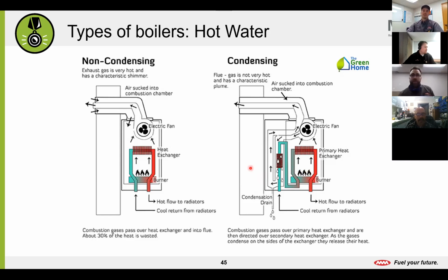All right. So boilers. I know Joe was talking a little bit about that on a condensing loop, right? If you're all running in heating, you're absorbing heat from that water. Eventually that water is going to dip below that 60-degree mark. That's where your boiler comes into play. So you'll have a thermostat mounted to your water loop and set for 60 degrees. When it reads that it's below that temp, it'll fire away, right?